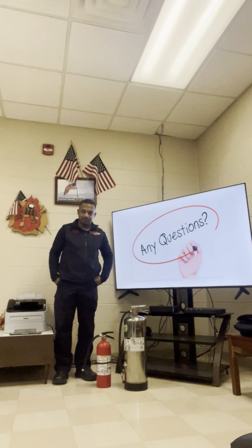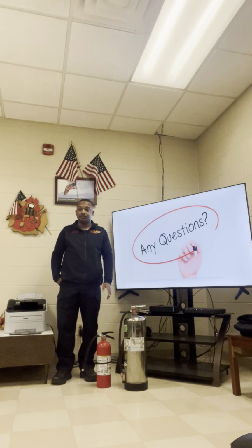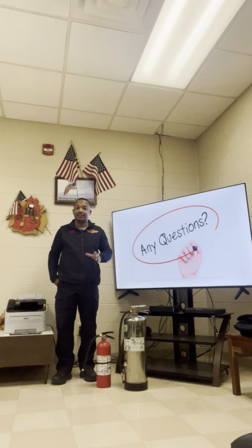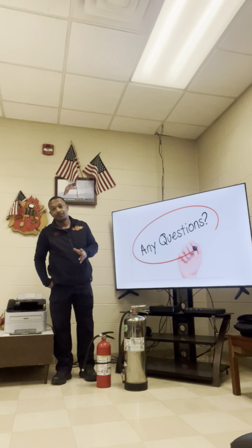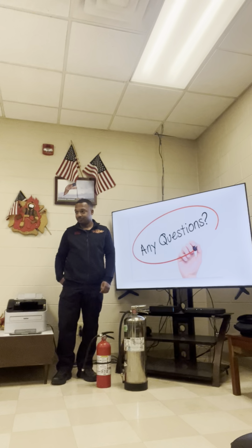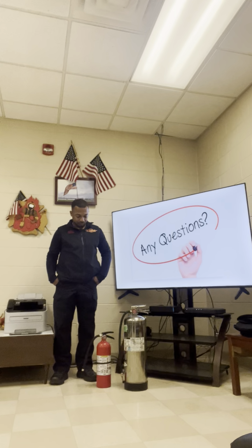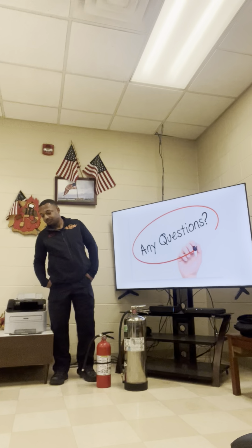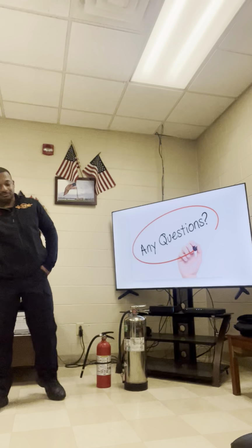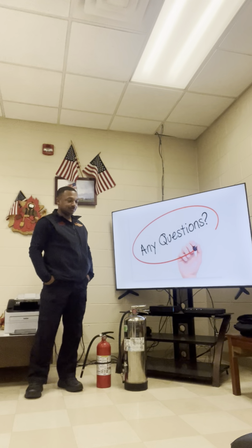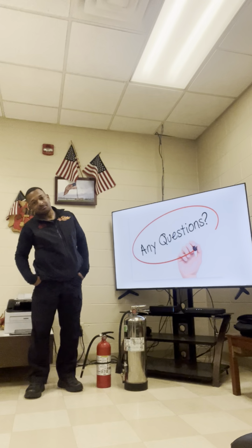So what would happen if I sprayed it on a grease fire? If you spray this one, the ABC dry powder, on a grease fire, it'll put it out, but it's not as effective as the Class K. Class K is designed technically for oils. The other one has water in it, so if you have that water base on oil, you can have the possibility of a flare. If you can get on top of it, it might put it out, but if the oil reacts to the water first, it's going to flash, just like that picture they had up there.